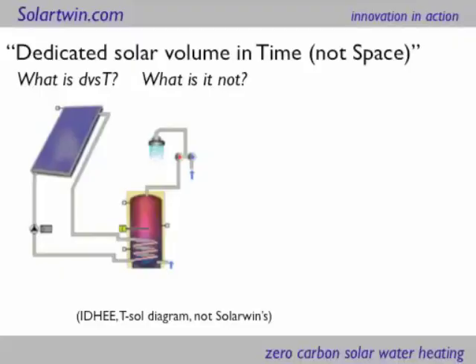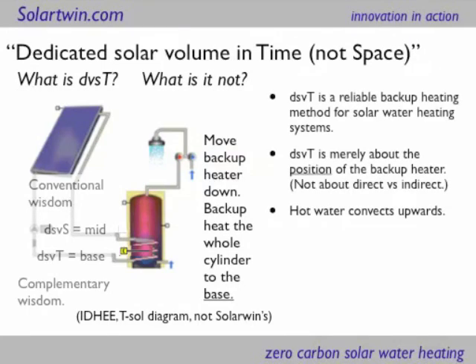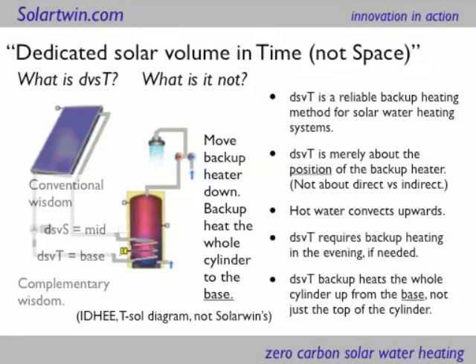Moving on to the explanation of what Dedicated Solar Volume in Time is, as opposed to space, which is what conventional solar does: here's a diagram of conventional solar in space, and the key thing is that little E on the left-hand side — the yellow plug — which is the immersion or backup heater. It's halfway up, which means you've got problems: a small volume above and an unheated volume below in winter. So what Solartwin do is remove that and stick it down at the bottom. That allows us to use an existing hot water cylinder, and we can back that heat up all the way to the base. It's reliable — it's only about the position of the backup heater, not about direct or indirect heating. The hot water convects upwards from that. The backup heating has to be on in the evening, not by day, but we do heat the whole cylinder.